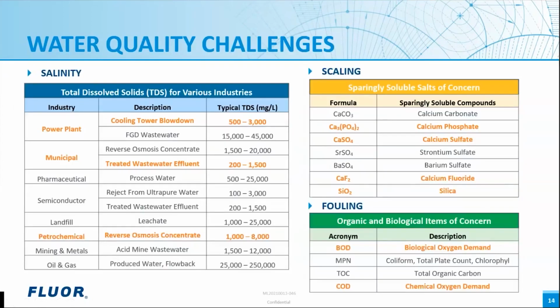This slide presents some of the water quality challenges when designing an MLD system, and the items of concern revolve around three categories, namely salinity, scaling, and fouling components. The figure on the left shows a typical total dissolved solids expected from liquid waste streams in a variety of industries. The most common range of salinity concentrations are highlighted in orange. The important point to note from this table is that as TDS increases, water recovery is more limited, water chemistry becomes more challenging to treat, and higher energy is required.